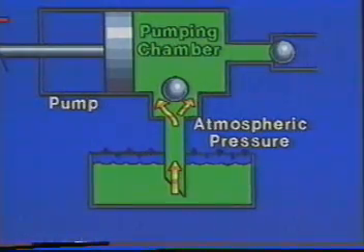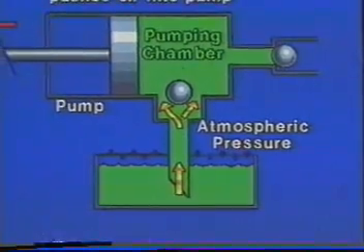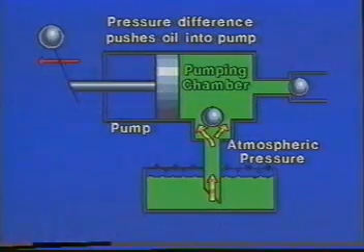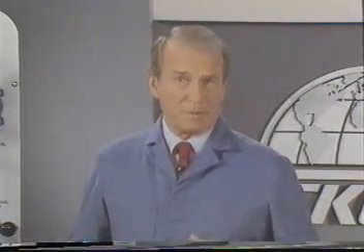Another thing, a surprising number of people think a pump sucks the oil out of the reservoir. It doesn't. A pump merely lowers the pressure at its inlet, and fluid is pushed in by the atmospheric pressure acting on its surface. Inlet lines are especially important because with only 14.7 pounds per square inch doing the pushing, any restrictions or even too thick an oil may cause the pump to starve. The technical word for this starving is cavitation, and it causes an erosion-type damage within the pump. An air leak at the inlet causes similar problems.